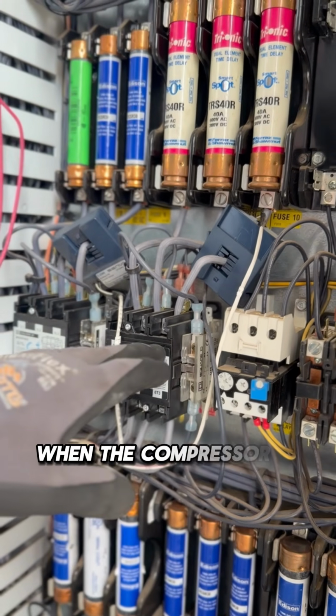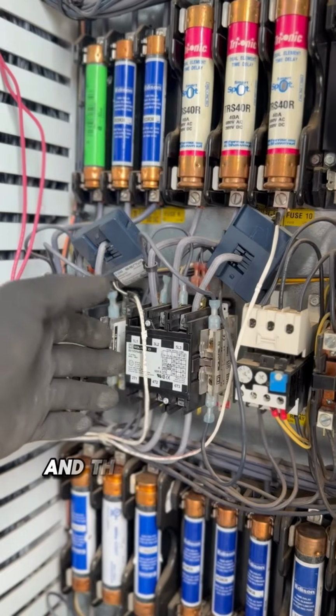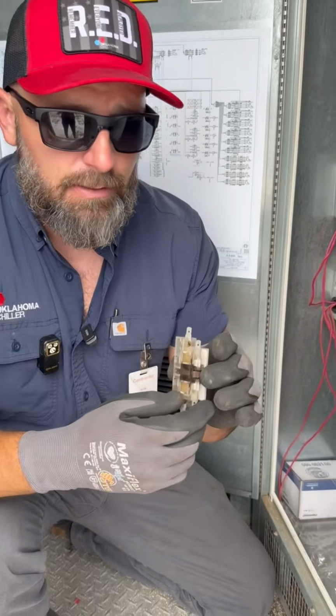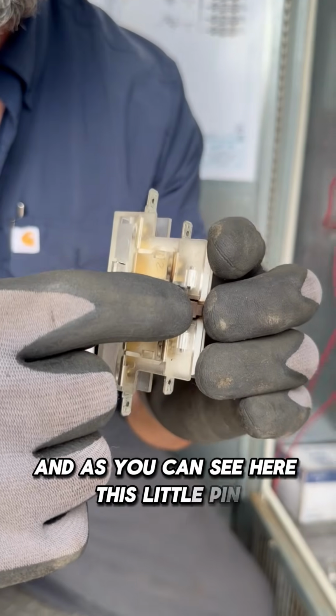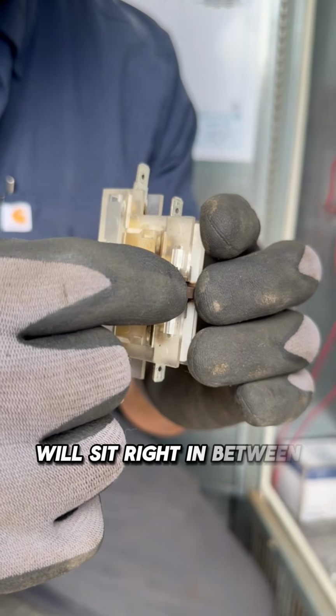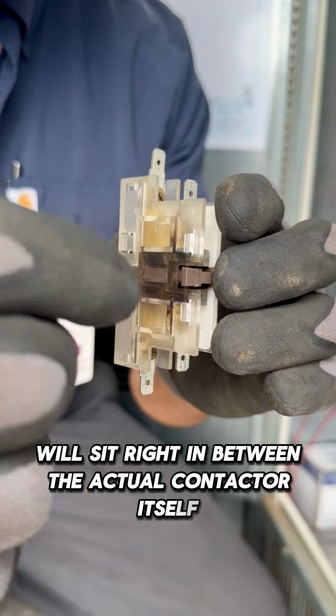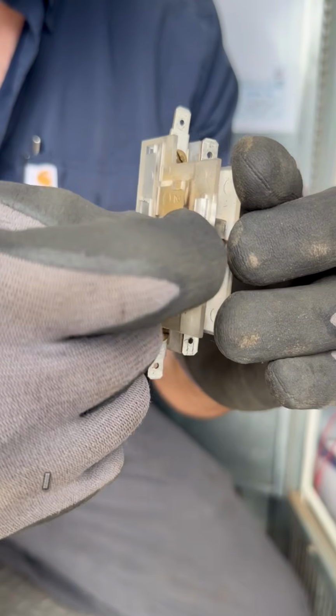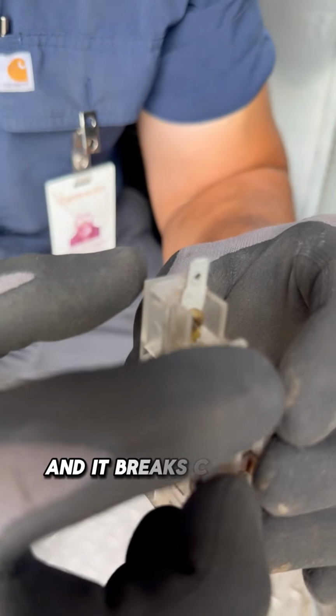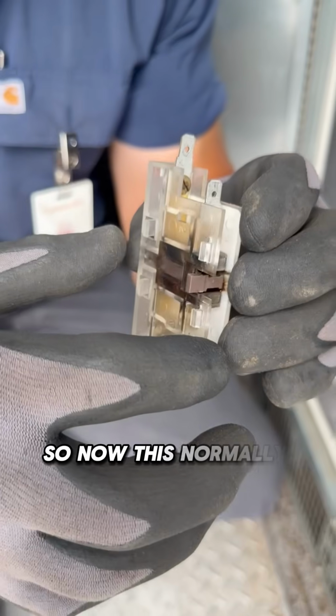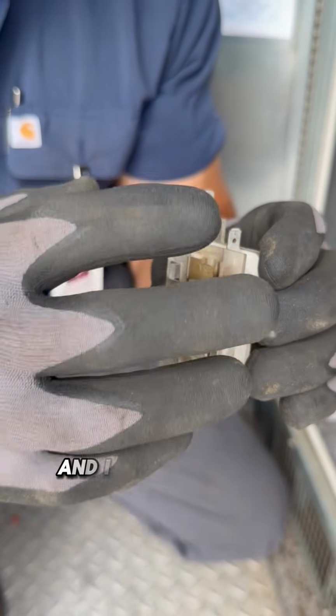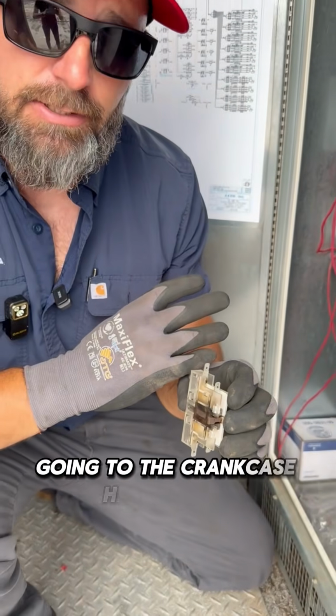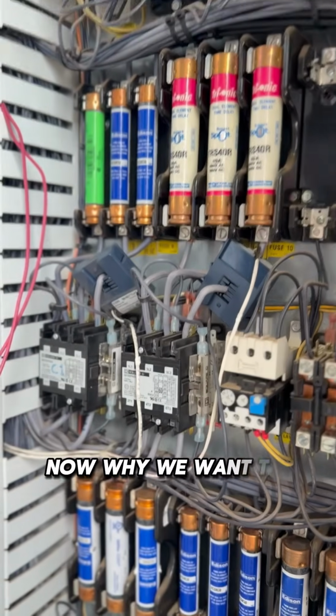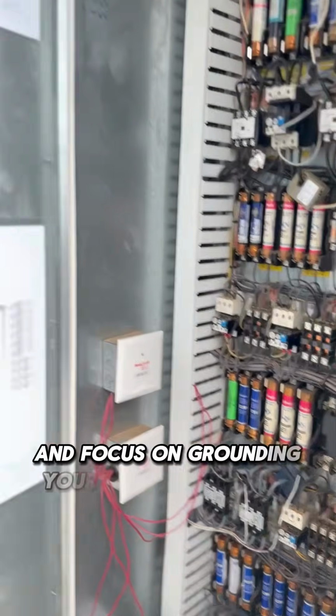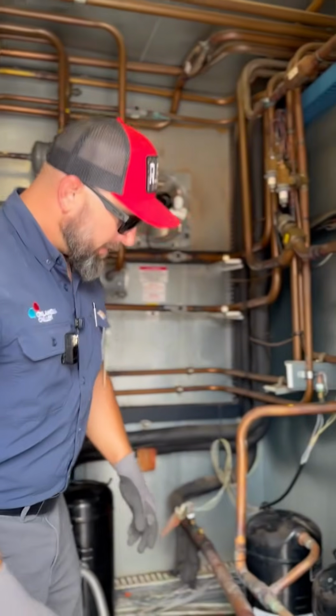This will power your crankcase heater strip when the compressor is not calling for cooling and the contactor is not pulled in. And as you can see here, this little pin will sit right in between the actual contactor itself. So when the contactor pulls in, it pulls this down here and it breaks contact from top and bottom. So now this normally closed switch is now normally open and it cuts off high voltage going to the crankcase heater strip. Now, why we want to talk and focus on grounding your crankcase heater strips.